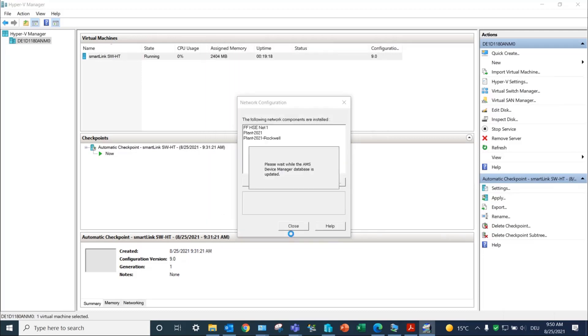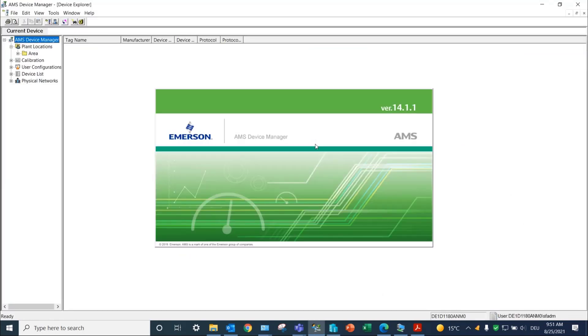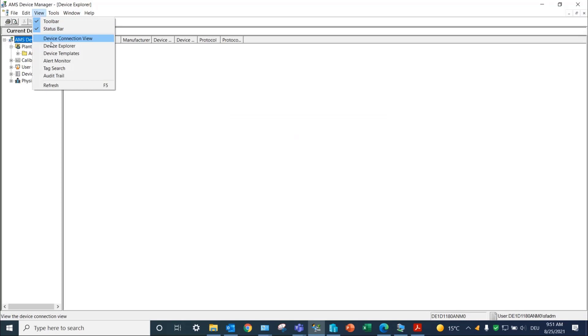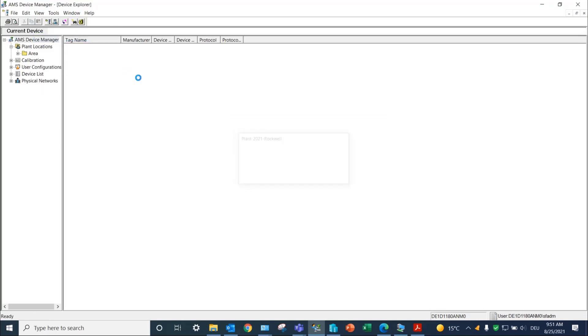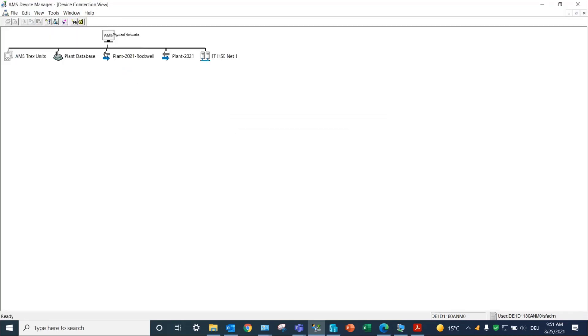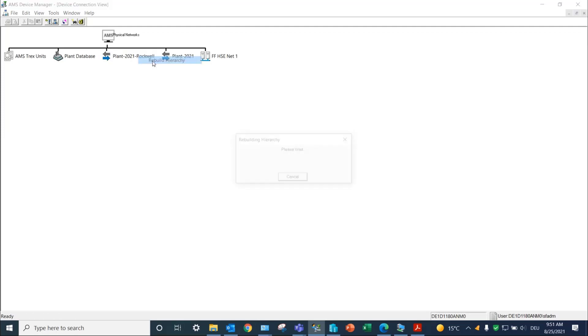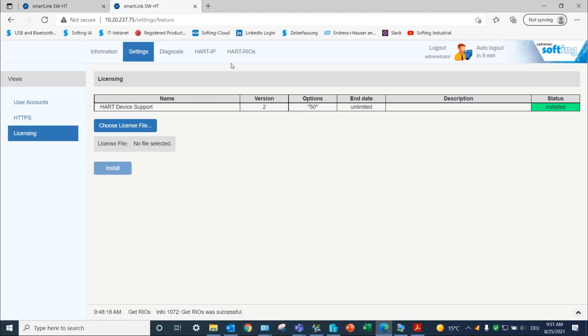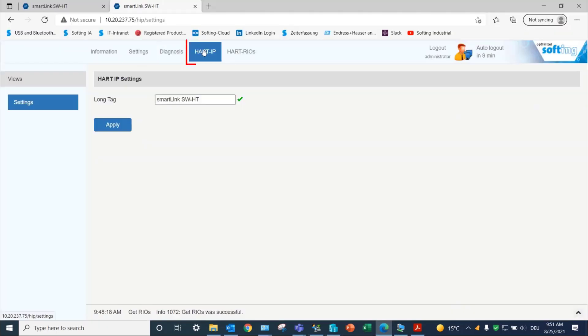Close the network configuration window and launch the AMS Device Manager tool. Your interface has been added under the chosen name. Click on Rebuild Hierarchy to get information from the live list of the SmartLink solution. The device will be recognized with its long tag name entered in the web interface under HART-IP Settings.